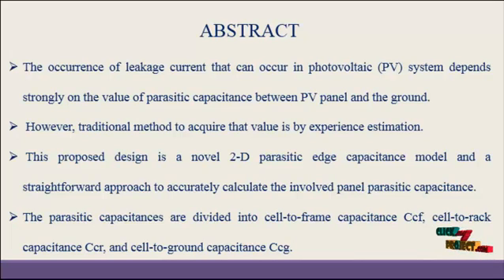The parasitic capacitances are divided into cell-to-frame capacitance Ccf, cell-to-rack capacitance Ccr, and cell-to-ground capacitance Ccg. Based upon that, a pi shape circuit model is derived to predict the leakage current in PV array. The approaches are very useful for the evaluation of leakage current in the PV system.